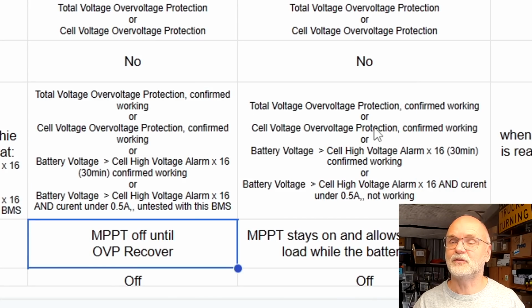All right, so this is now the trigger for setting the BMS back to 100%. Battery voltage over cell high voltage alarm times 16 for 30 minutes. And then it resets to 100%. So if you're one of these persons who are wondering why the BMS resets to 100%, that is why.